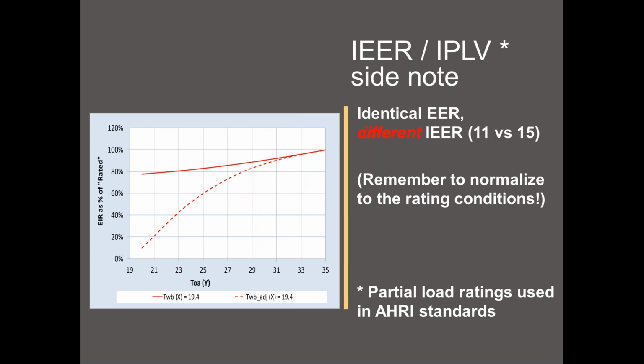EER is defined, and actually Matt referenced it in his slide, as BTUs per hour of cooling capacity divided by the input power in watts. So it uses different units, BTUs per hour on the top and watts on the bottom. However, it generates a little larger number. So the EER of 11 is so much capacity in BTUs per hour divided by the watts of input power.